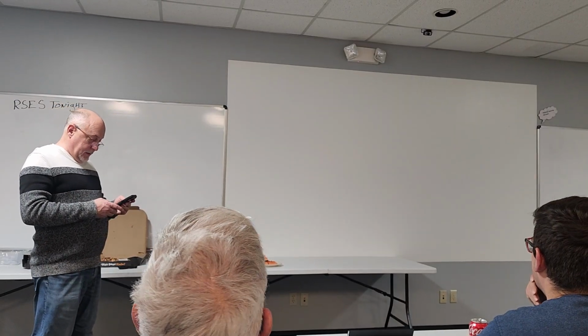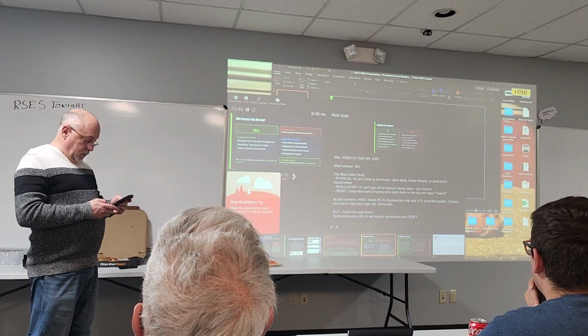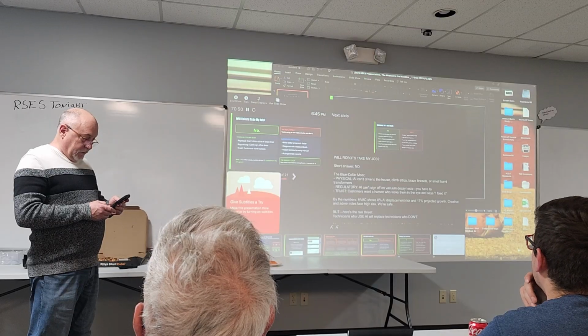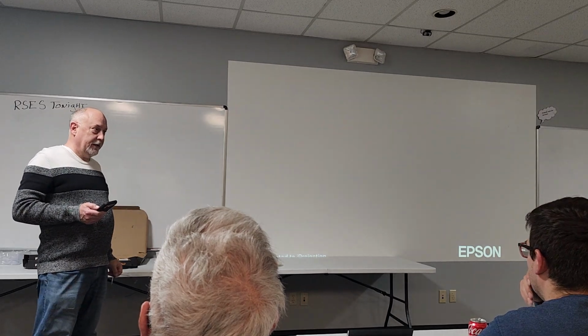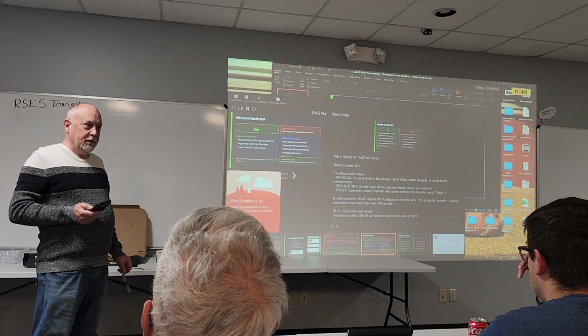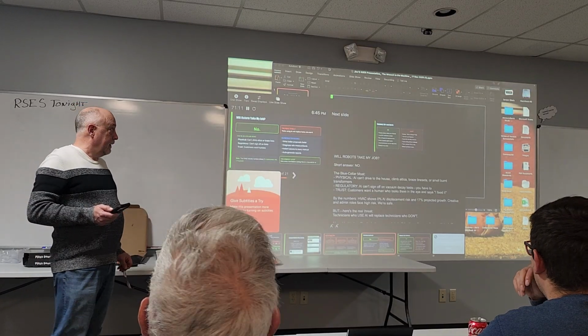Well, this is the same issue that we have. One of the biggest problems we have is technicians that tell the service manager what the service manager wants to hear, right? So what's your superheat? It's about 10 degrees. What's your subcooling? Then what's a good service manager ask next? What's your saturation temperature? What's your line temperature? Well, that doesn't equal 12 degrees of superheat, or what you have.